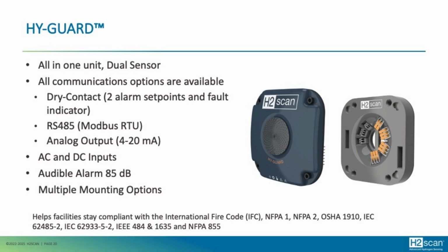So it is an all-in-one unit that is very popular in the battery industry. Actually, the battery industry helped design this unit to the specifications that they need, but it also does very well for most all safety applications in which you're trying to detect an accumulation of hydrogen. So this is a general location sensor. If you need Class 1 Div 1, Class 1 Div 2, or those kinds of intrinsic safety applications, we have sensors that meet those requirements. So this has safety certifications for electrical safety, and it's, like I said, very popular in battery rooms, data centers, and also energy storage containers.